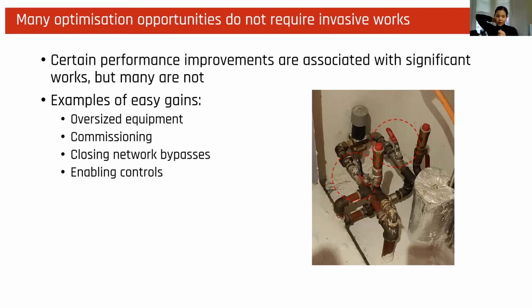A second very common but very simple work to carry out to improve network performance is to close network bypasses. And to illustrate this, I've featured this image to the right, where we can see a top of riser bypass that's open between the flow and the return on the network, where closing this bypass is merely a case of pulling these two levers and ensuring that they're being kept closed. Two other very common work items that were suggested that are relatively cheap and very easy to enable for is to enable controls and carry out commissioning of equipment.